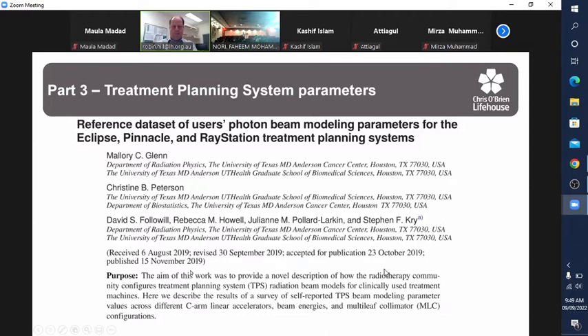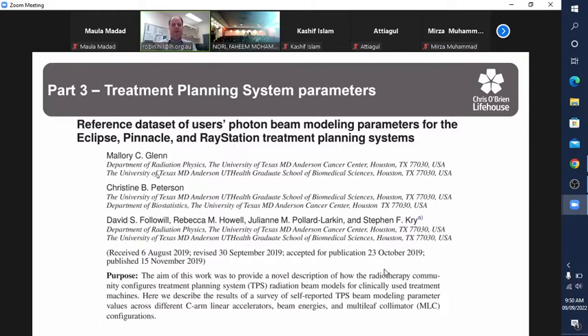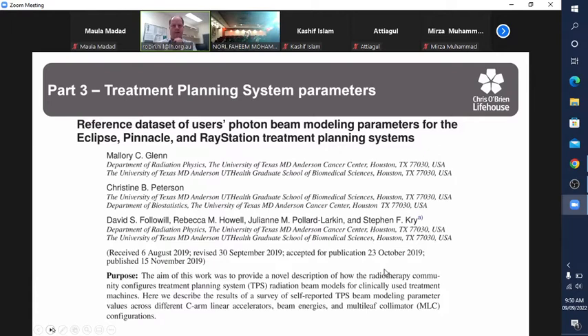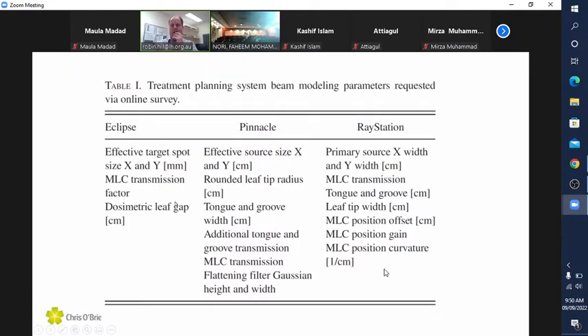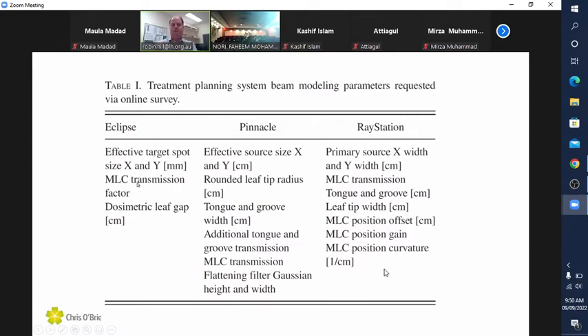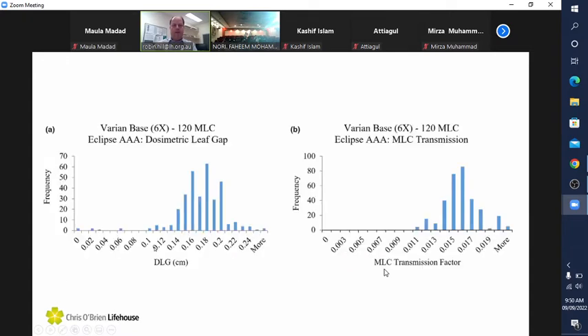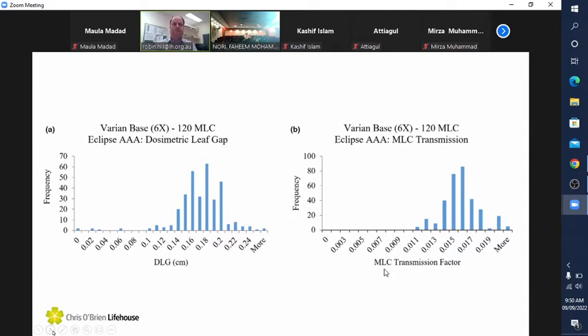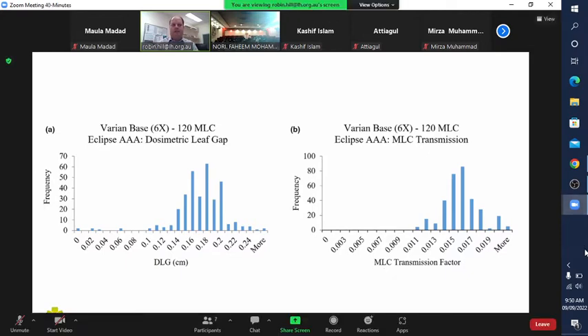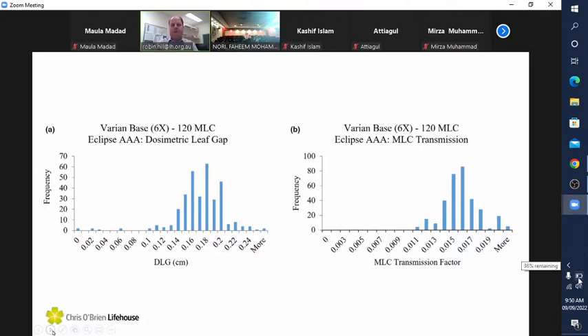The more recent publication from 2019 was looking at some of the beam modeling parameters for Eclipse, Pinnacle and RayStation. This is really important for small field dosimetry for those who have Eclipse: your spot size, your MLC transmission and your DLG. They have taken data from all their centers for the AAA and Acuros algorithms and plotted those, with tables of average values for these particular parameters.